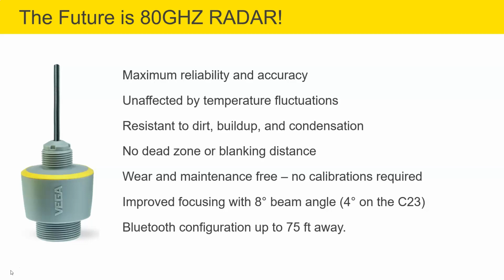You also get improved beam angles to minimize the effects of buildup on vessel walls or internals such as pipes and pumps. And we can set everything up via Bluetooth, which makes it much easier to configure a device when you don't have to get right up to it in a nasty environment, or if it's just simply pouring down the rain.